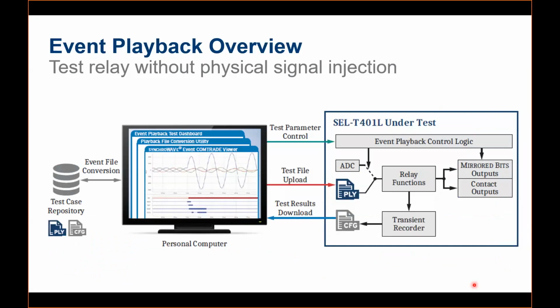Unfortunately, I don't have the concept of digital twin, but actually it's kind of a utility that you can use to test and validate the functions or the results of the field results. For example, there is a field relay that has operated on one of the disturbances or faults, and it has created a fault record. But you doubt the performance of the relay, the speed, selectivity, or any other issues.